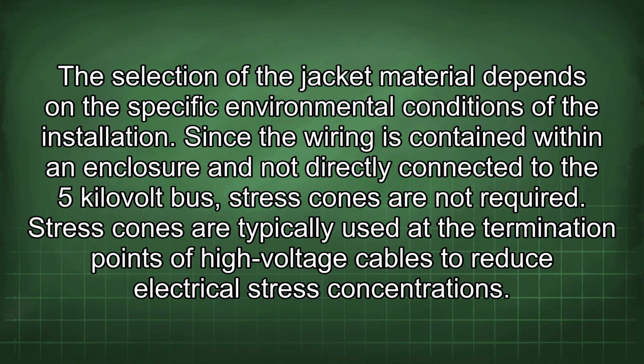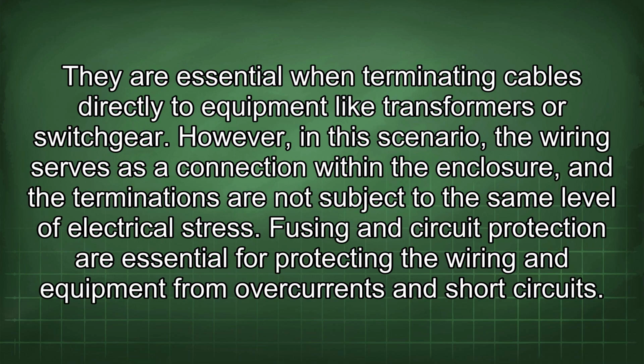Since the wiring is contained within an enclosure and not directly connected to the 5 kV bus, stress cones are not required. Stress cones are typically used at the termination points of high voltage cables to reduce electrical stress concentrations. They are essential when terminating cables directly to equipment like transformers or switchgear. However, in this scenario, the wiring serves as a connection within the enclosure, and the terminations are not subject to the same level of electrical stress.